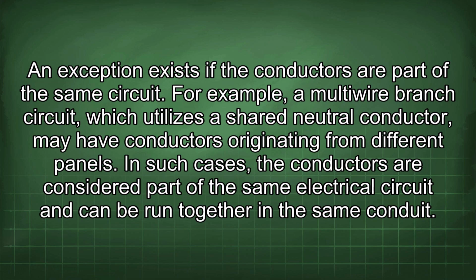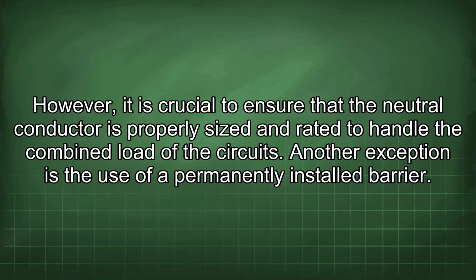For example, a multi-wire branch circuit, which utilizes a shared neutral conductor, may have conductors originating from different panels. In such cases, the conductors are considered part of the same electrical circuit and can be run together in the same conduit. However, it is crucial to ensure that the neutral conductor is properly sized and rated to handle the combined load of the circuits.